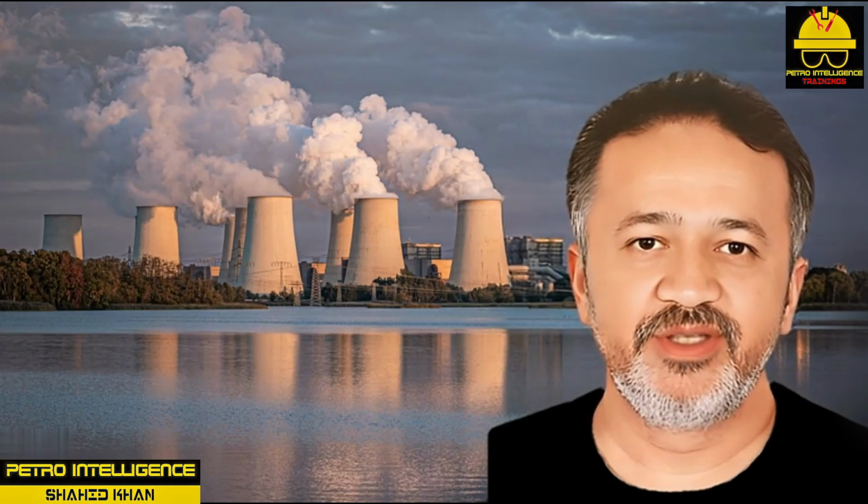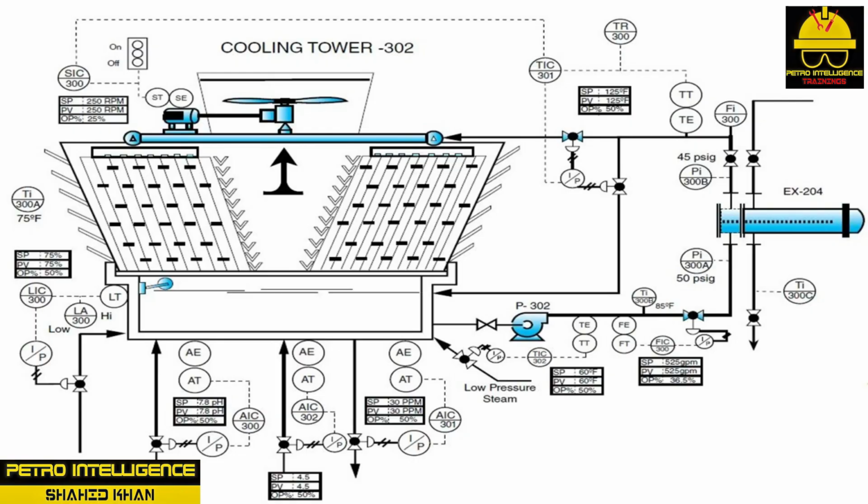Fan 300 failure. CTW302 operates the fan when temperatures and relative humidity reach predetermined levels. During the winter months, the fan is rarely operated and the hot water bypass system is frequently used. A spare motor, gearbox, and fan blade arrangement are located in the maintenance shop. Several days, however, are typically required for large projects. It is possible to operate the cooling tower in a natural draft condition.